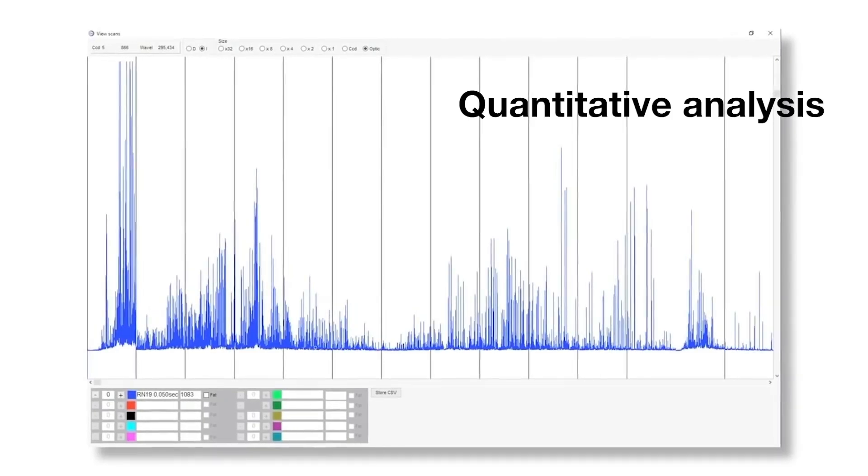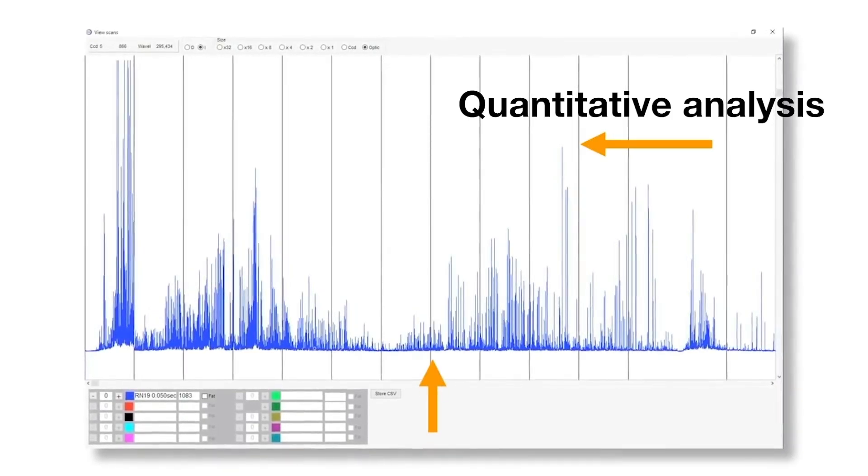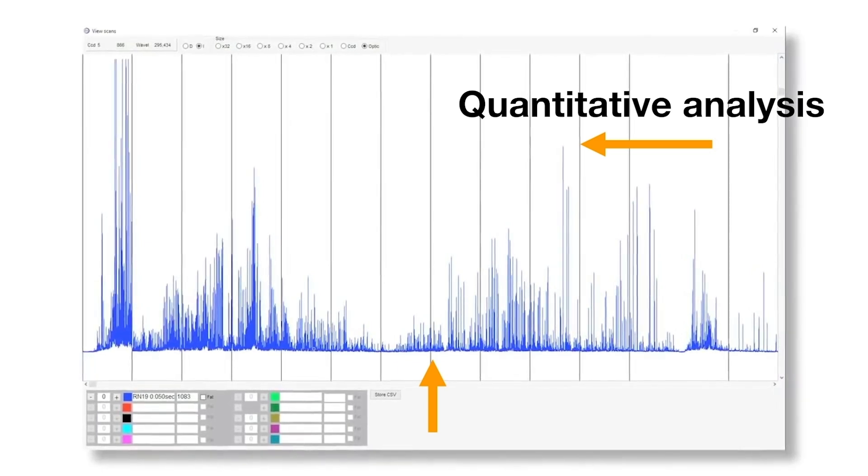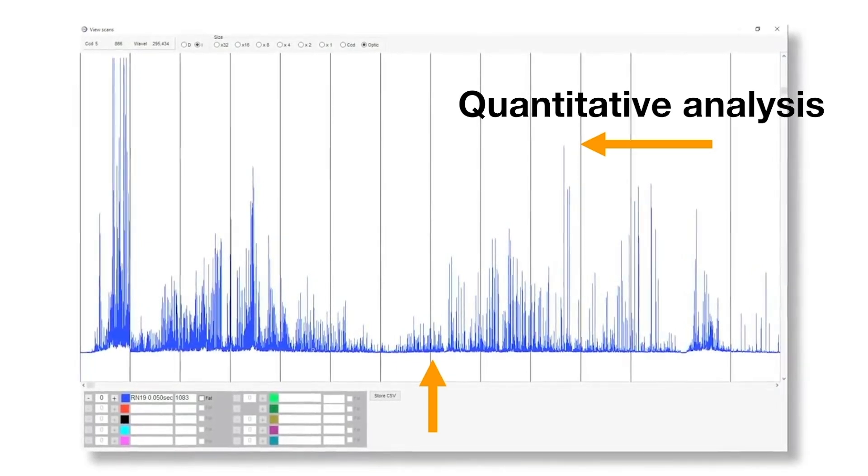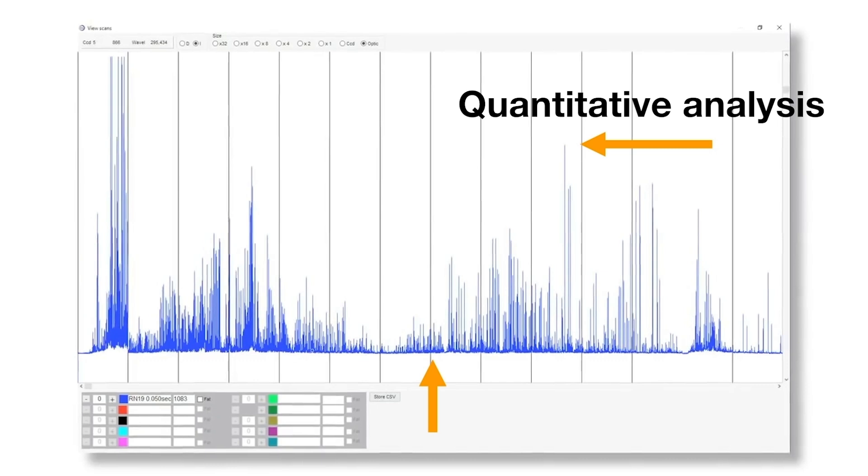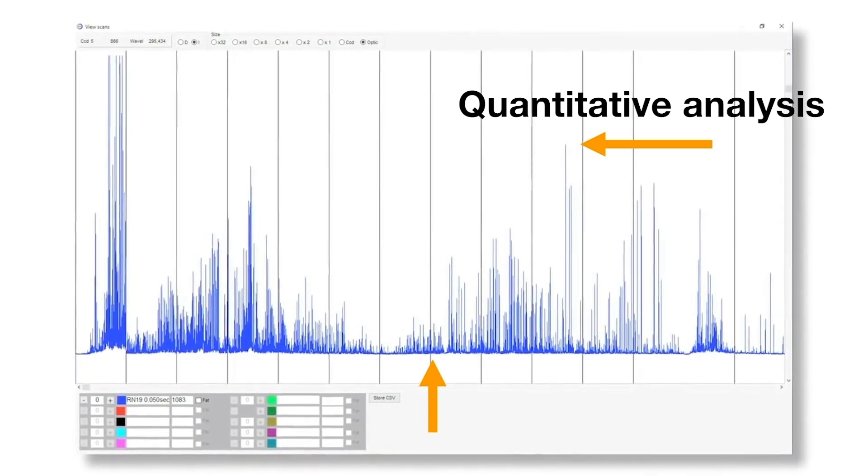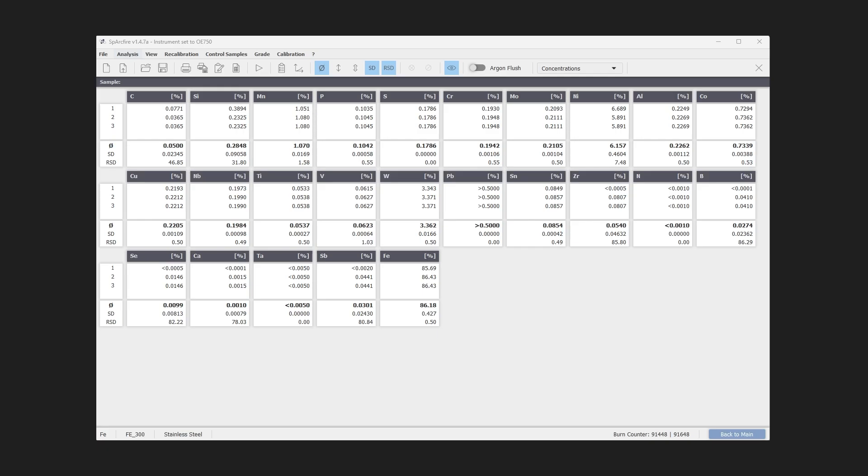However, OES is also a quantitative technique. As we can see, the peak wavelength identifies the element and its peak area or intensity gives an indication of its quantity in the sample. The analyzer then uses this information to calculate the sample's elemental composition based on a calibration with certified reference material.